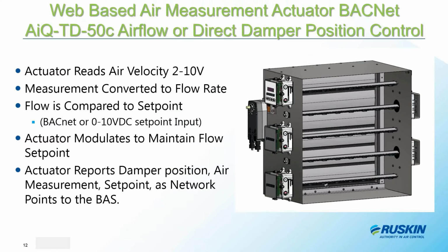Again, there is not a separate controller. The set point controller is built into the actuator, and it interfaces directly with the building automation system. It has two operating modes. Flow control is CFM set point. The built-in controller utilizes an internal PI control loop, proportional integral control loop, and it's fast and precise. And that's via the BACnet interface.